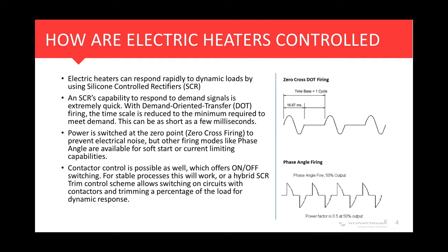There's also the simplified control scheme, which would be using just contactors for on-off control. That basically means you have 100% power when demand is needed and no power when it's not. Ultimately, you can combine that with an SCR to have what's called a hybrid SCR control scheme, to try to balance out either a large load or to throttle the SCR side of it.